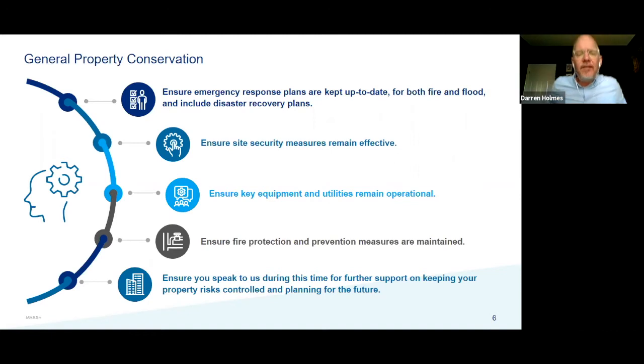Other areas to consider are key equipment and utilities - making sure vital facility fuel tanks, for example where you have backup generators, are topped up with diesel. This is particularly relevant where you've got fire pumps for sprinkler systems. Check that emergency generators are still working - a weekly check to run them up and ensure they're working, and that you have access to a fuel supply should you need it, particularly in large warehouse locations.